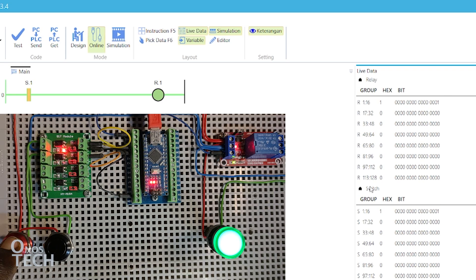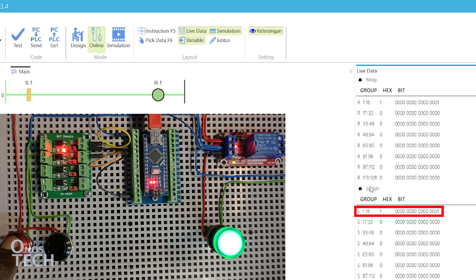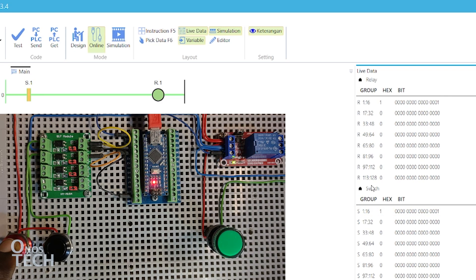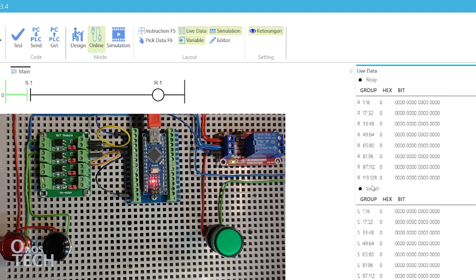Observe that the rung condition in Outseal Studio becomes true and R.1 coil changes color to green. On the Live Data window, the rightmost bit of Group R1 column 16, which represents the coil state, is now 1. The rightmost bit of Group S1 column 16, representing the contact, is also 1. Release the switch and see that the bit changes to 0.